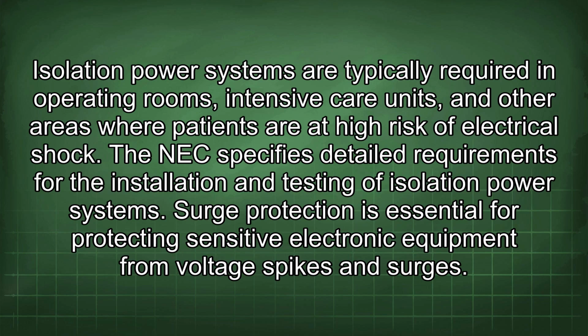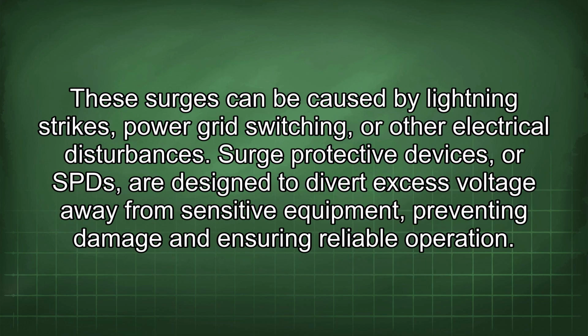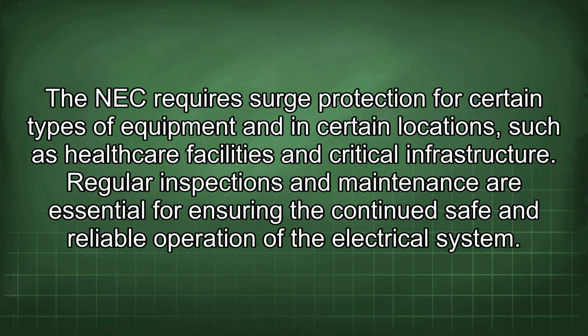Surge protection is essential for protecting sensitive electronic equipment from voltage spikes and surges. These surges can be caused by lightning strikes, power grid switching, or other electrical disturbances. Surge protective devices, or SPDs, are designed to divert excess voltage away from sensitive equipment, preventing damage and ensuring reliable operation.